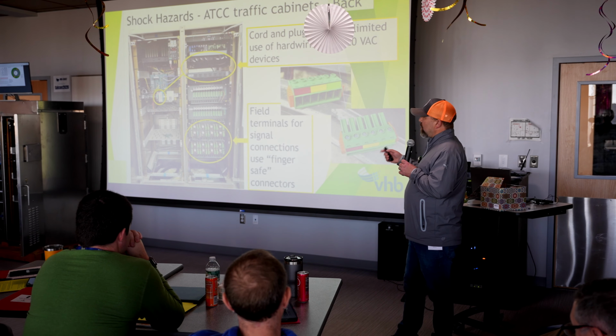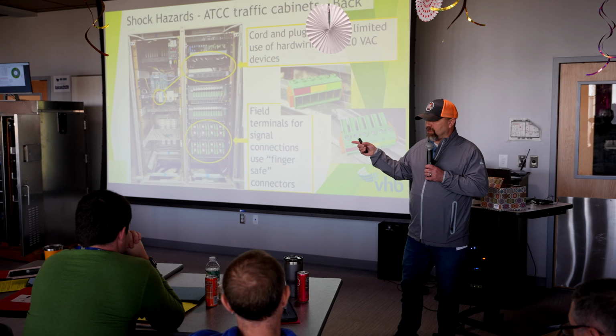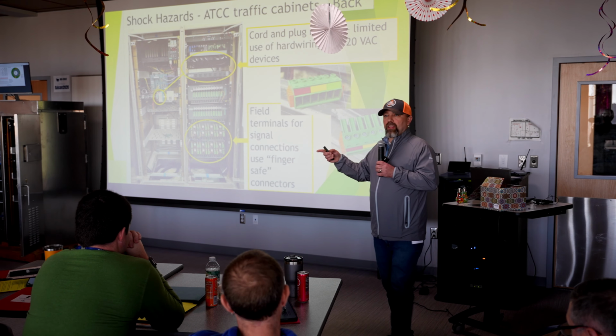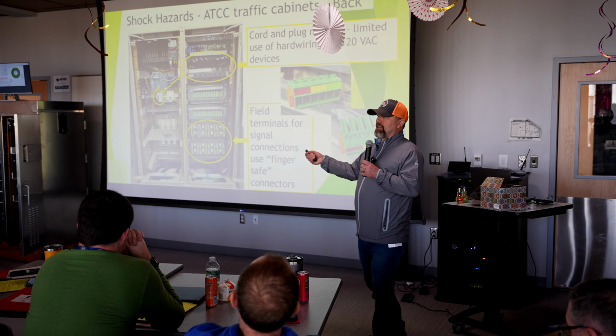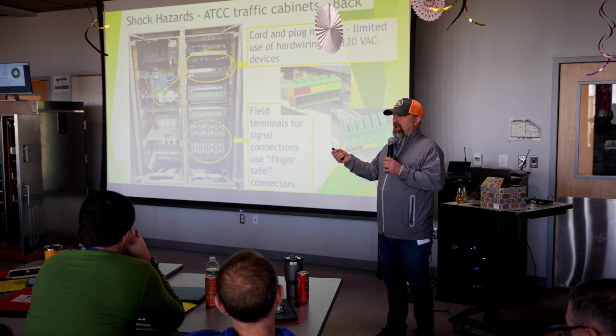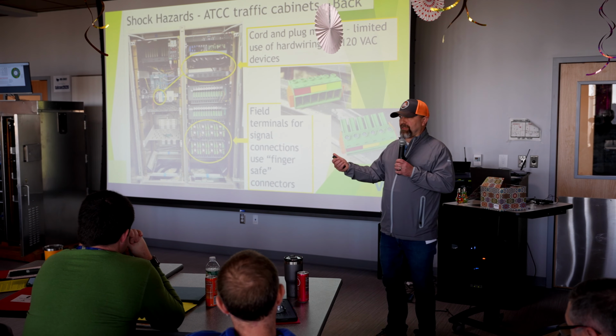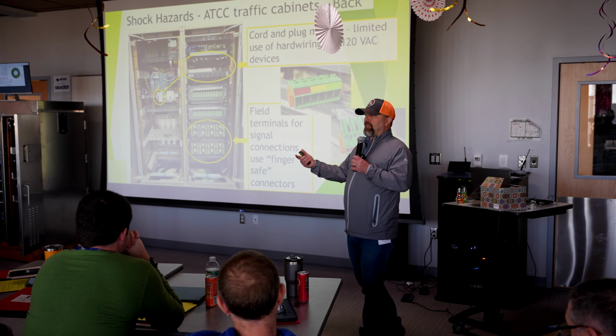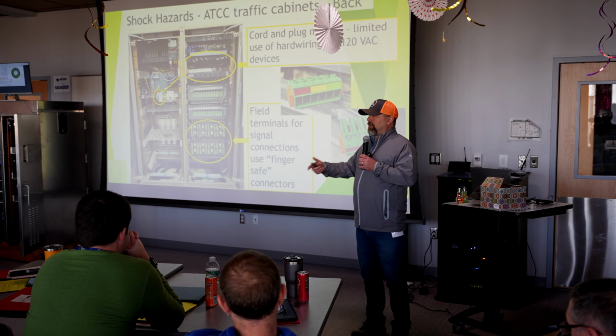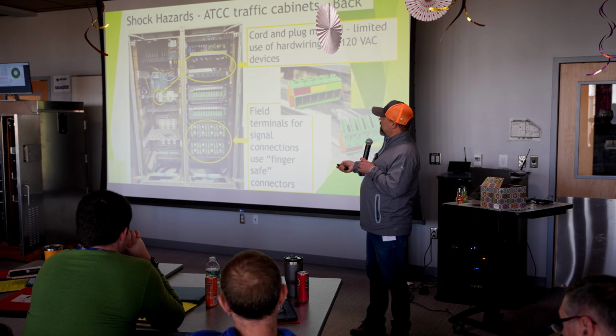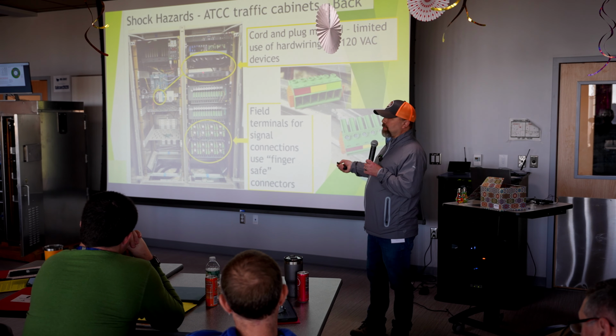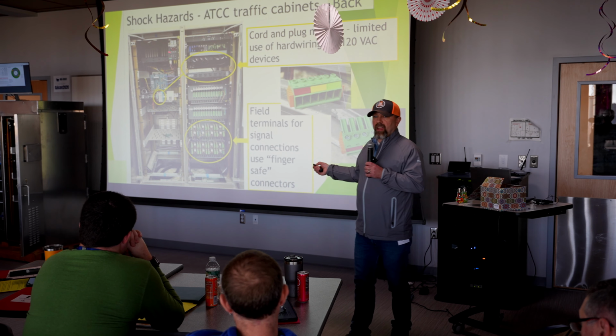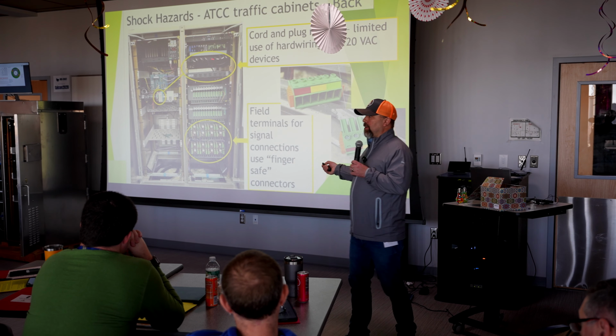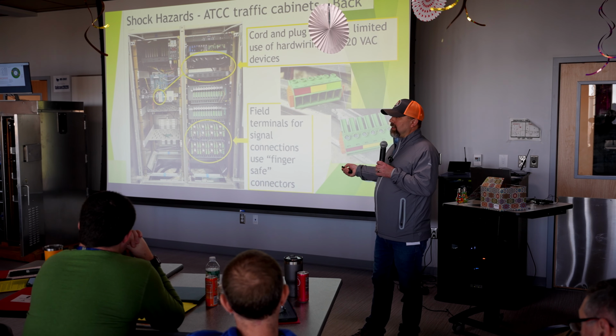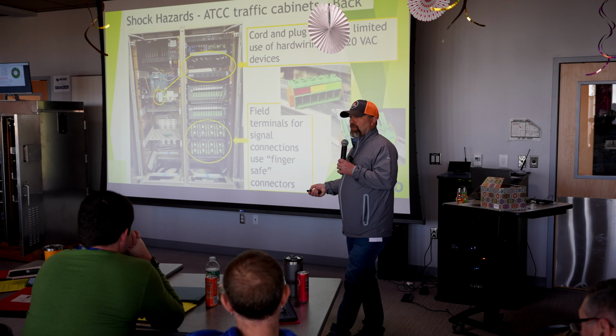Yeah, so on these cabinets, and this is in the state spec, you have a dedicated service receptacle that's on the outside of the cabinet. It should have a breaker, typically a 15 amp breaker with a GFI receptacle. So when you're showing up and doing work, you're really not looking to plug drills or other high current devices in here, because this is what's called a clean electrical bus.